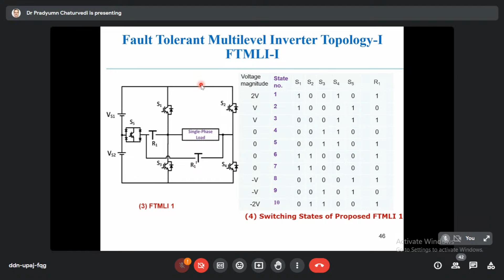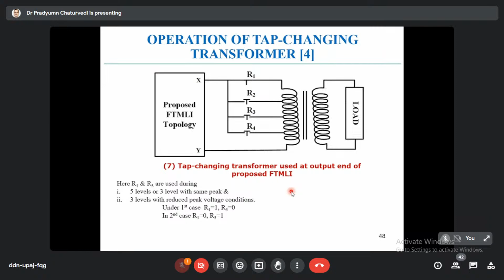So this tap changing transformer will do that. Under normal operation, this R4 is closed, for example. If some fault occurs in S1, S2, voltage will be reduced to half. So then we can turn on R2, so more voltage can be given to the load. So just by tap changing, offline or online tap changing transformer, we can do this, but it is not a practically feasible or efficient way of stepping up or boosting the voltage.